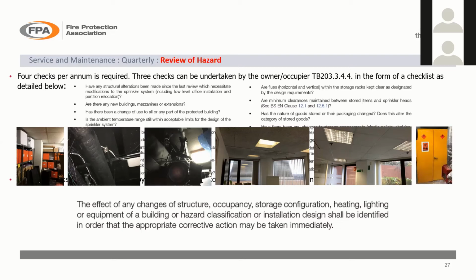And finally, on this particular slide, we've got a hazard chemical cupboard which had been put into a sprinkler pump room, containing lots of flammable materials, actually in a sprinkler pump room. So if you get a fire in that particular instance, that would potentially wipe out the 2 fire pumps that are there to protect the building from fire in the first instance. So it's not good practice. It needs to be moved, and it is dangerous. And that kind of thing, obviously, a hazard review would pick up. So that's just a few little examples across that particular screen.